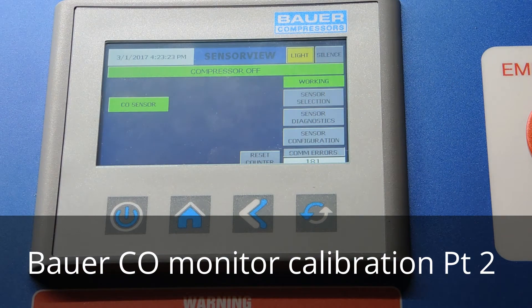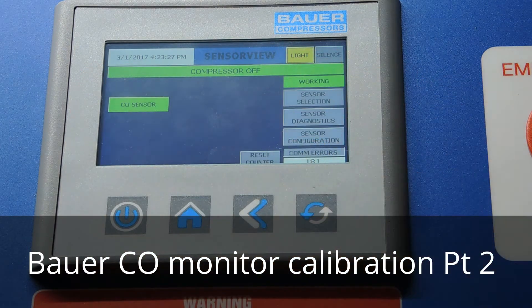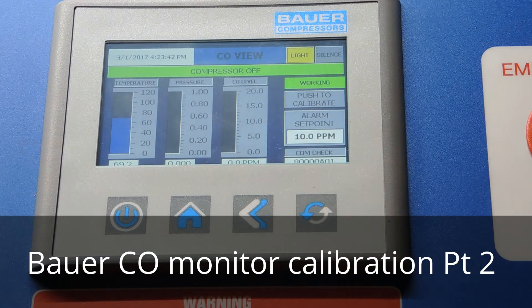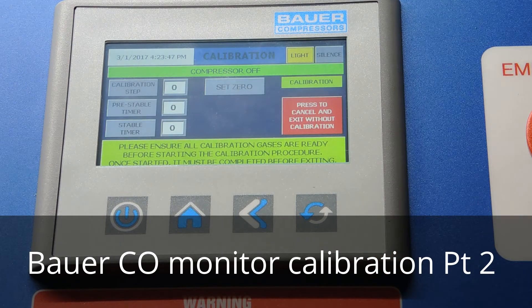We do need to log in whenever we do a calibration. We're going to hit CO View, which gives us the temperature of the cell and the pressure — of course it's not running so there's no pressure. We have zero parts per million of CO because we haven't calibrated it yet. We're going to go ahead and press 'push to calibrate.' There are some warnings here.